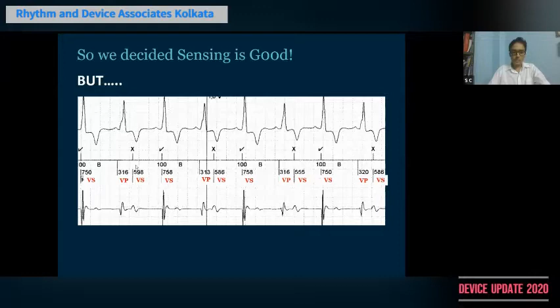So suppose you have this QRS and a prominent ventricular sense. You can see here ventricular sensing is corresponding with a T wave. This is sensed by the pacemaker as an intrinsic event, and it can actually inhibit pacing till the next base rate interval is over and the next VP occurs.